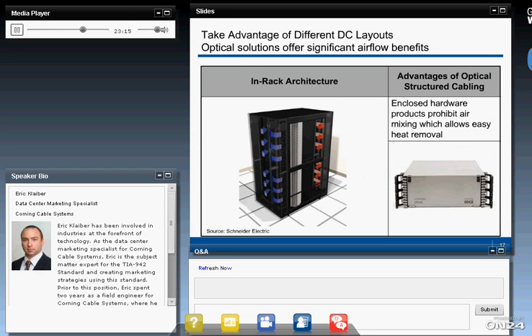Inside each rack, when we start doing this hot aisle, cold aisle sort of thing, what we see is we have to pass cold air, and you can actually see this is from Schneider Electric here. Cold air is coming in the front, going through certain things, and then going out the back. Now, those certain things we want to be the electronics, because that's what needs to be cooled. If the electronics aren't cooled, if the air is just passed through, it's doing no work. And what we really want is for the energy we put into cooling the air going into our data center to be able to perform some work by cooling the actual servers and actual switches that are doing all of our revenue generating within our data center.